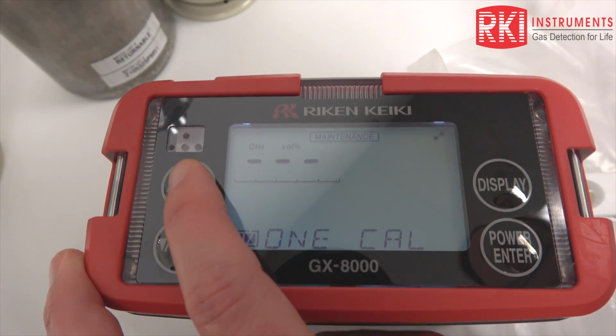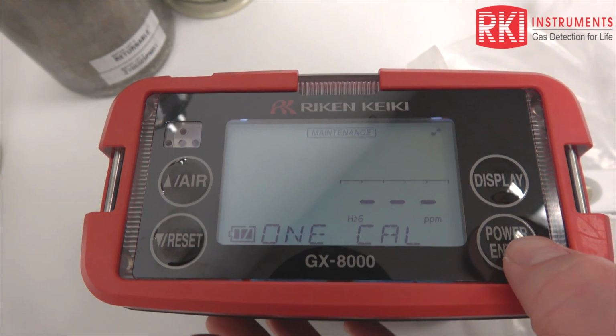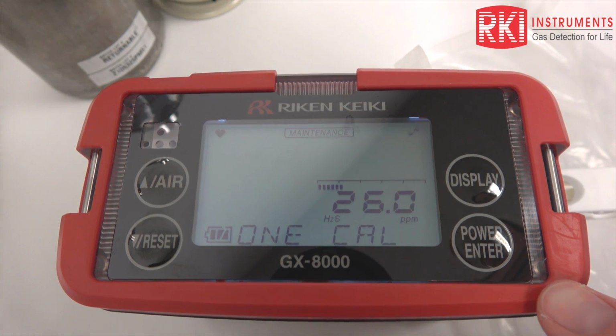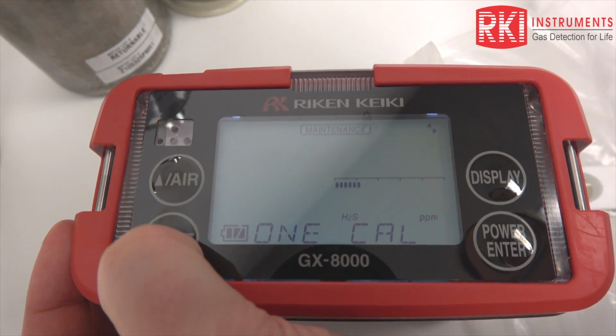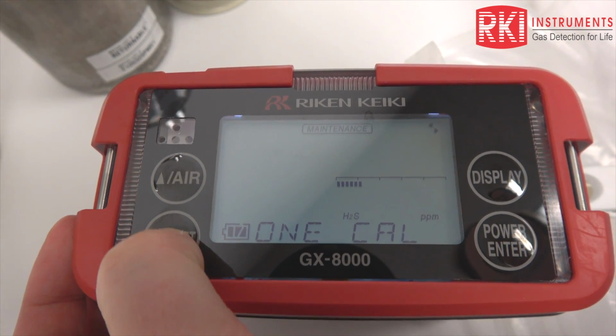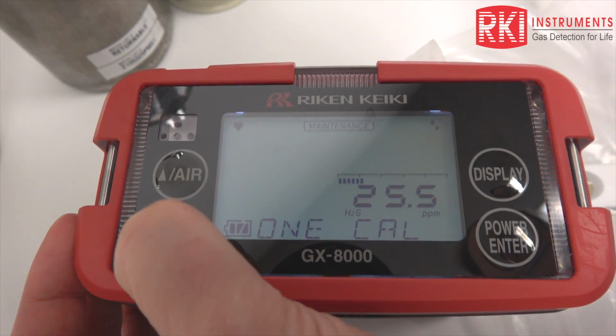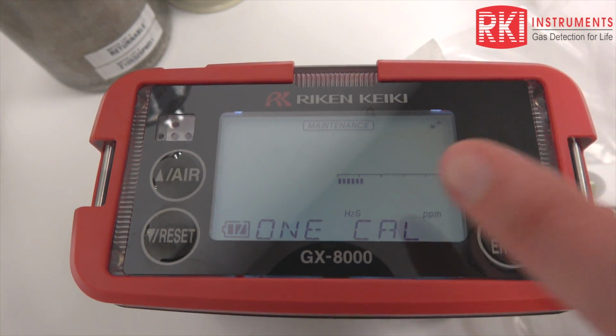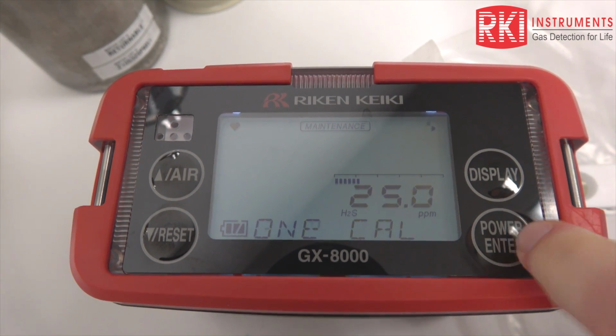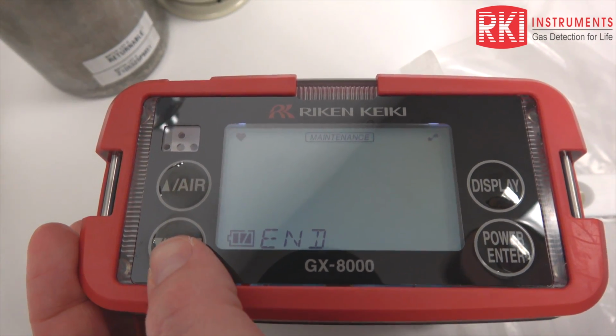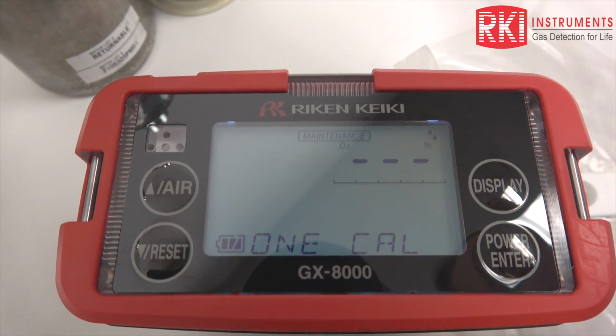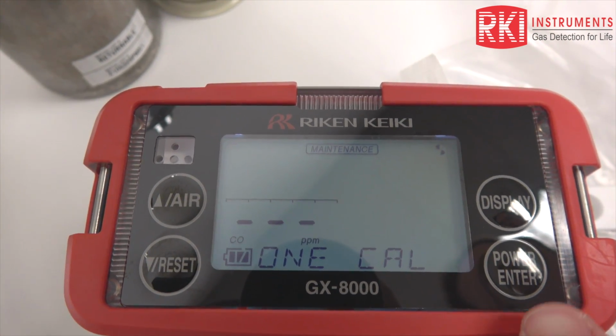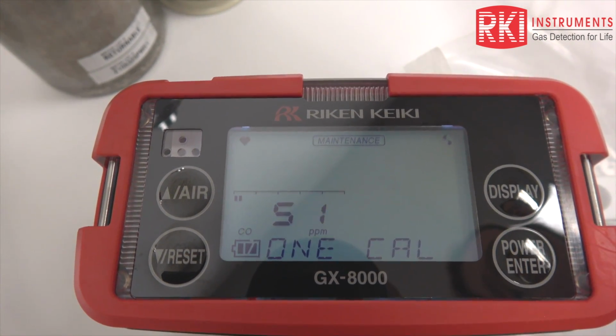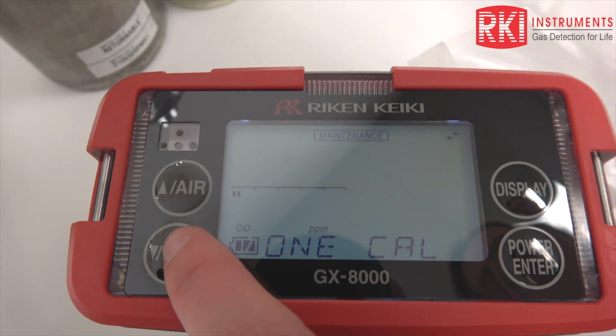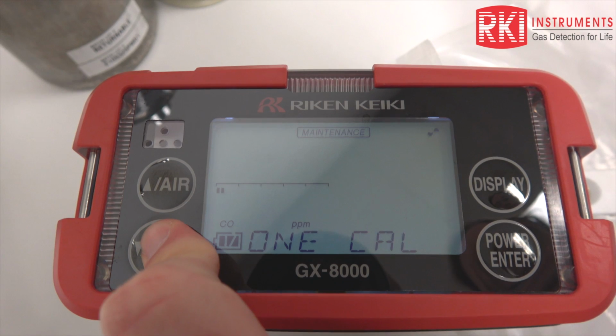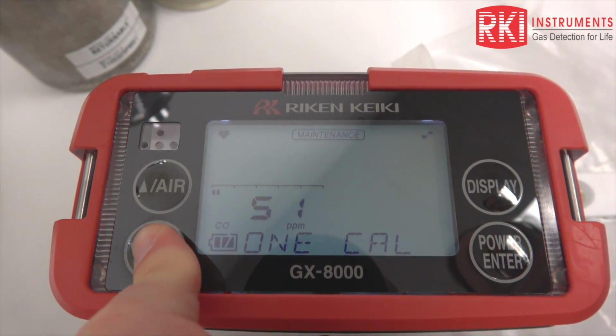And I'm going to move on to my H2S. I have 25 ppm H2S here. I just need to bring that reading down to match the concentration in my bag. So push enter, and then I'm going to move on to the CO. Again, I have a 4-gas mix in this gas bag, which is why I'm doing these 3 sensors at the same time. I have 50 ppm CO, so I need to bring this reading down.